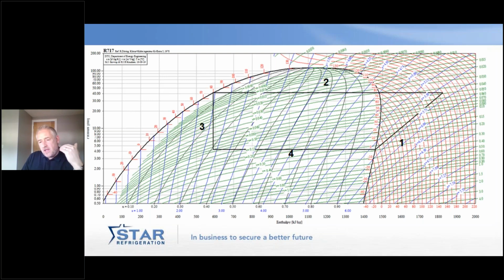Heat recovery, which is commonplace in many processes, takes something warmer and transfers heat to warm something cooler, but not any higher than what we started with. Heat pumps, quite literally as the name says, pump heat uphill - just as a water pump does. We're boosting heat in this cycle from round about 0 degrees, which is what we're cooling down, up to 80 degrees.